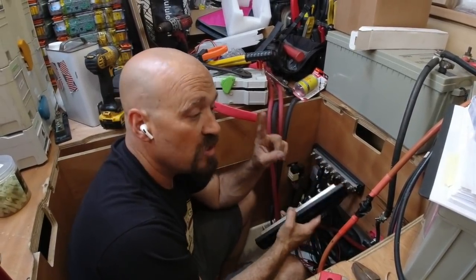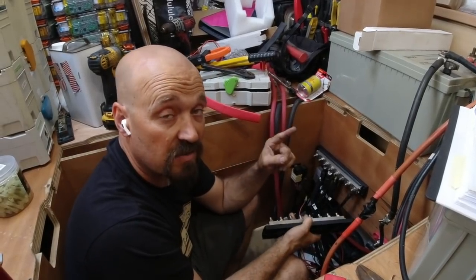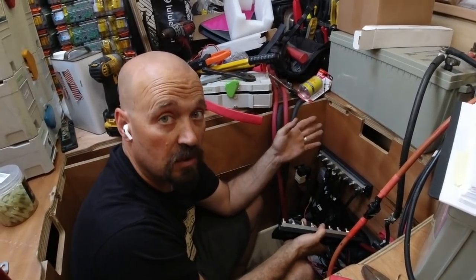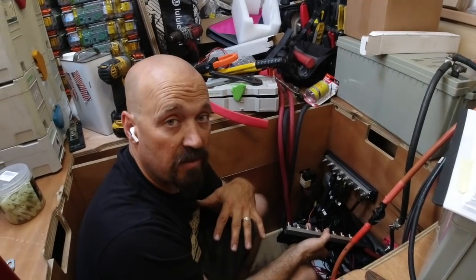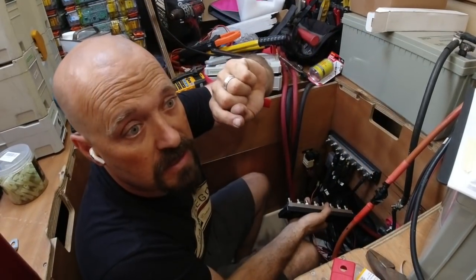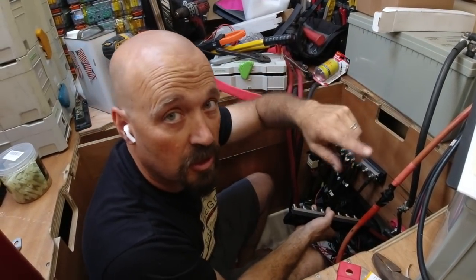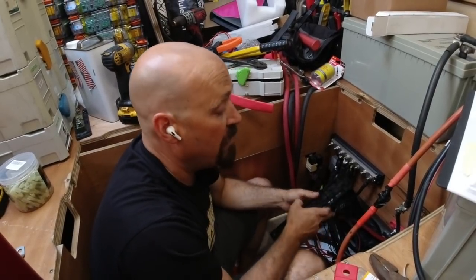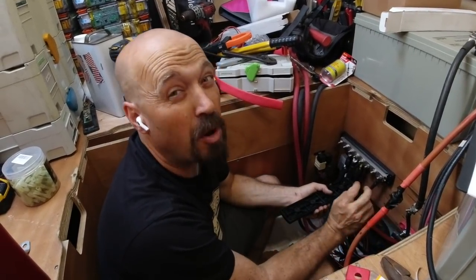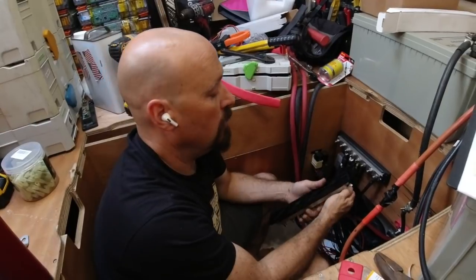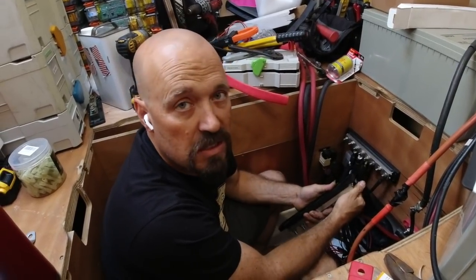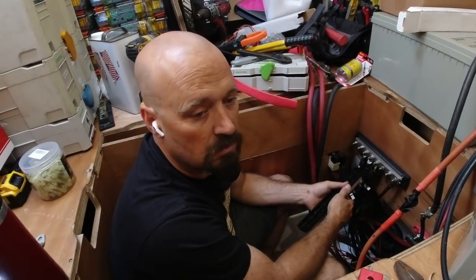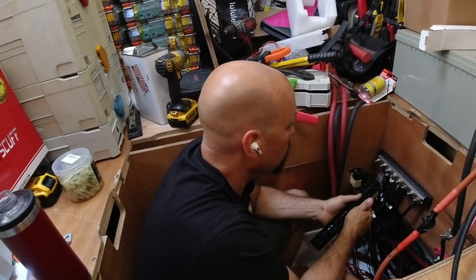However, we're going to have 2 distinct DC positive systems. One is 48 volt, which is what our batteries, our Tesla batteries, run on in series, and feed our massive inverter charger that's 15,000 watts. And then the small bus bar will be for our smaller loads like our winch and our windlass and lights and heads and bilge pumps and all of that.